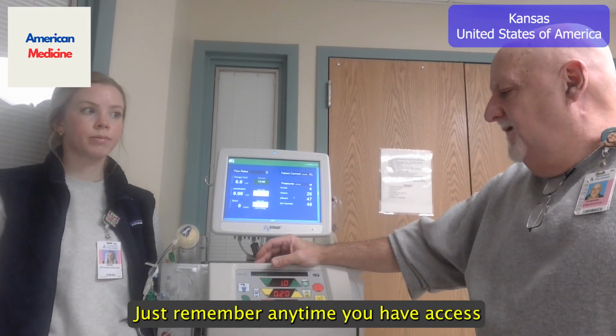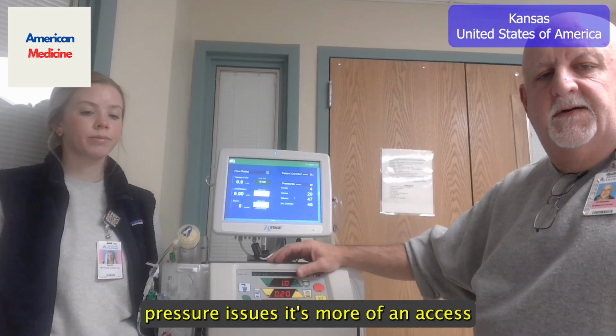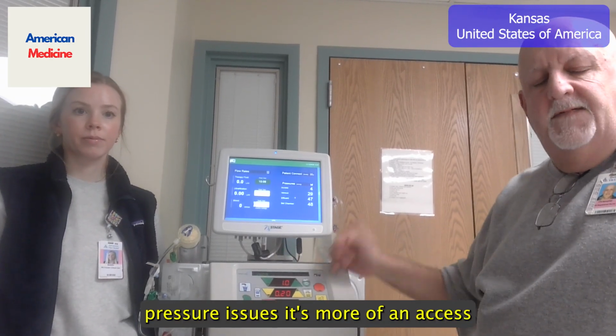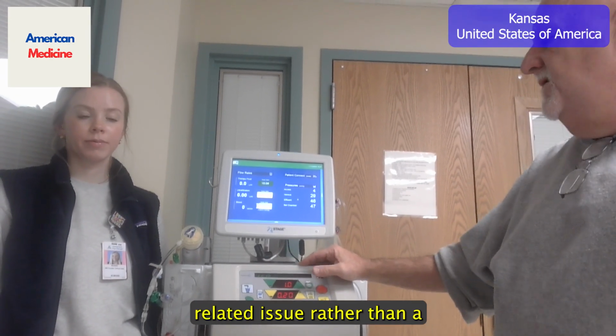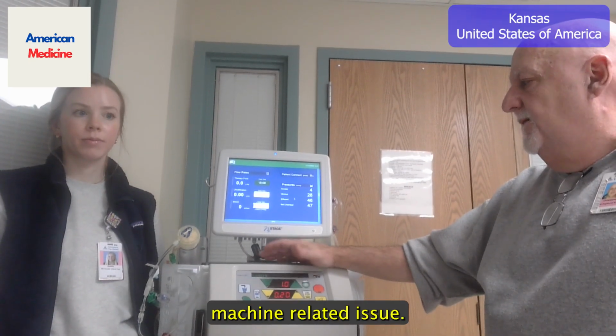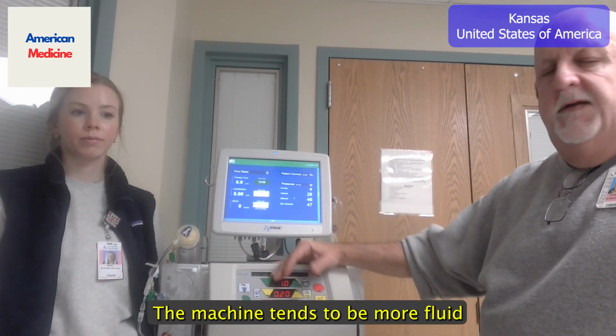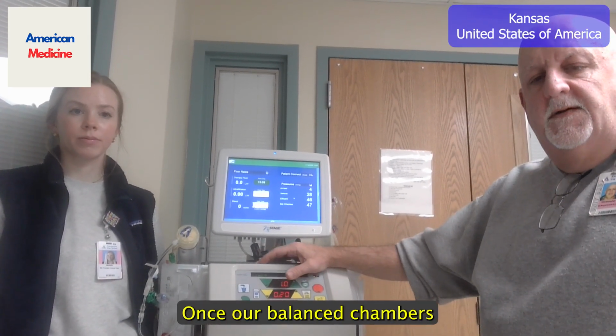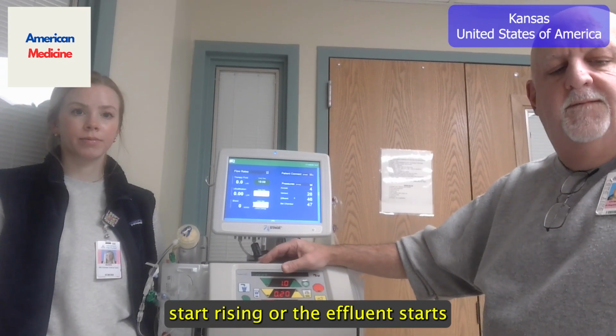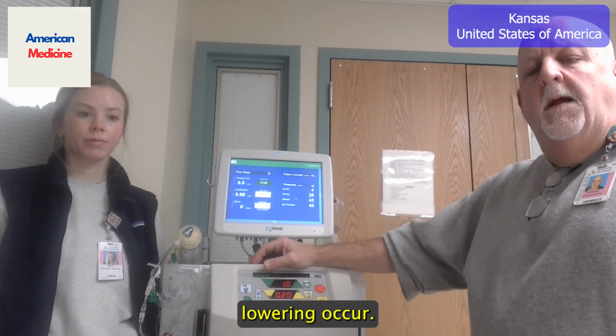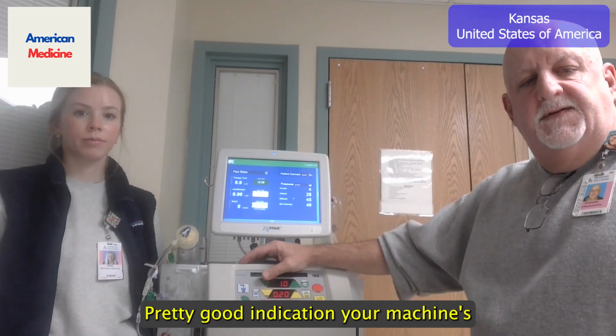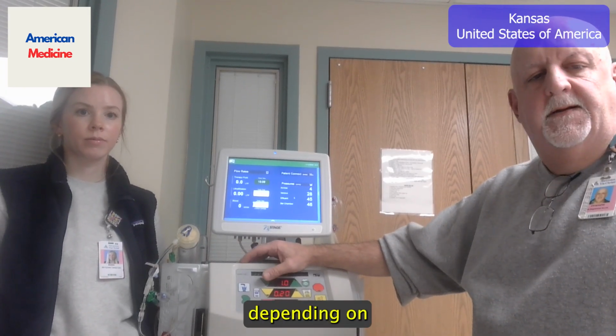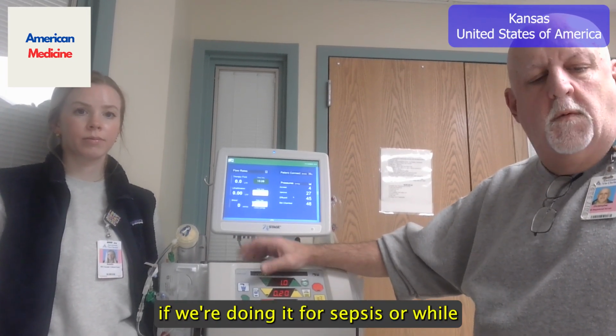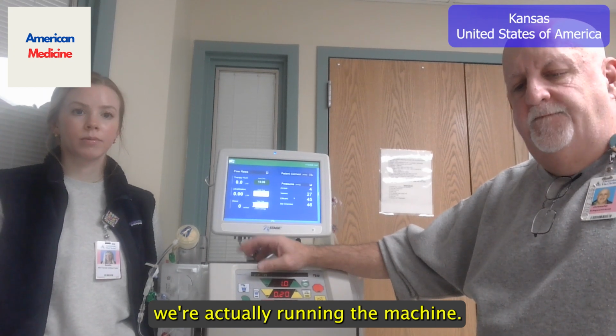Just remember, anytime you have access pressure or venous pressure issues, it's more of an access related issue rather than a machine related issue. The machine tends to be more effluent or balance chambers. Once our balance chambers start rising or our effluent starts lowering, it's a pretty good indication your machine's going to clog off, depending on if we're doing it for sepsis or why we're actually running the machine.